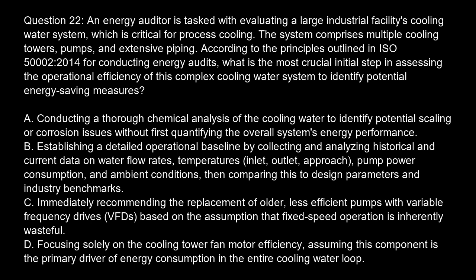Option A. Conducting a thorough chemical analysis of the cooling water to identify potential scaling or corrosion issues without first quantifying the overall system's energy performance. Option B. Establishing a detailed operational baseline by collecting and analyzing historical and current data on water flow rates, temperatures, inlet, outlet, approach, pump power consumption, and ambient conditions, then comparing this to design parameters and industry benchmarks.